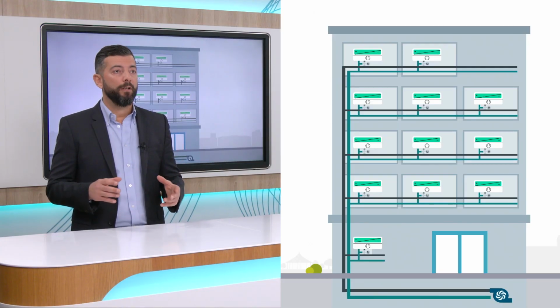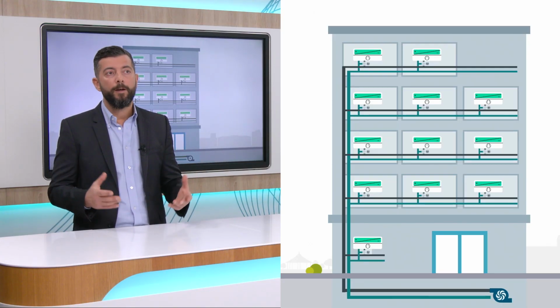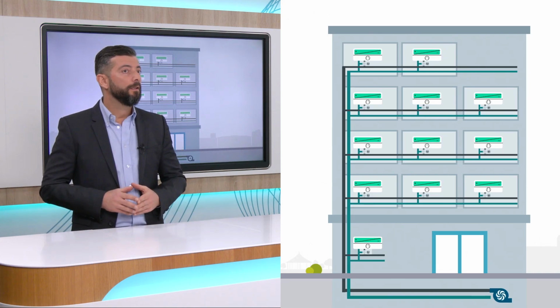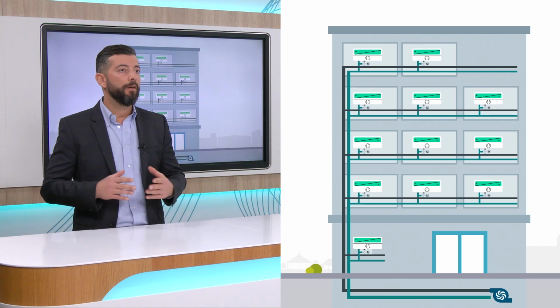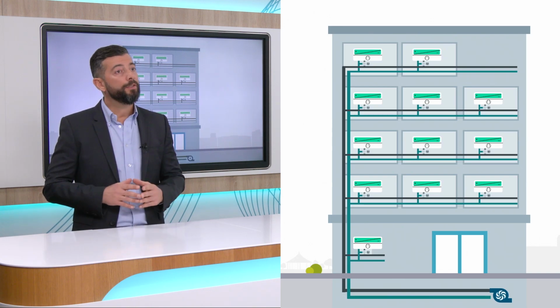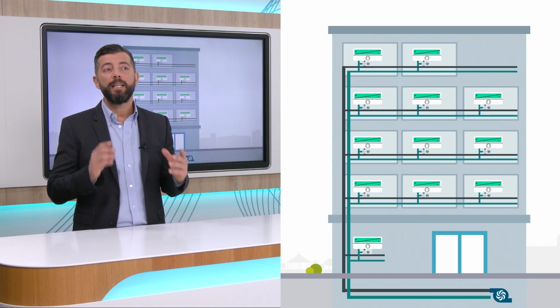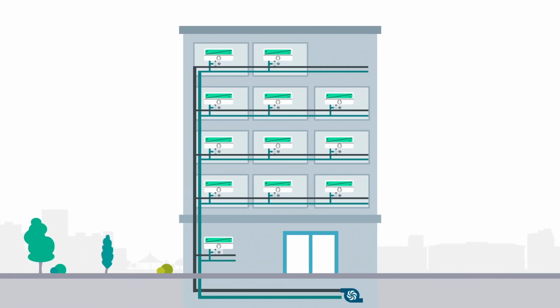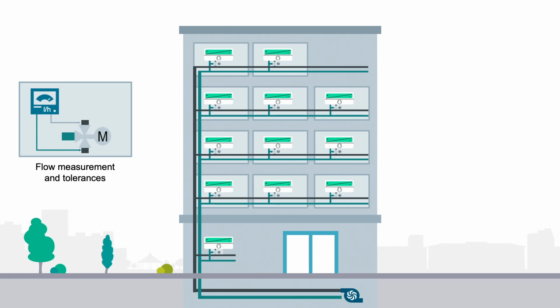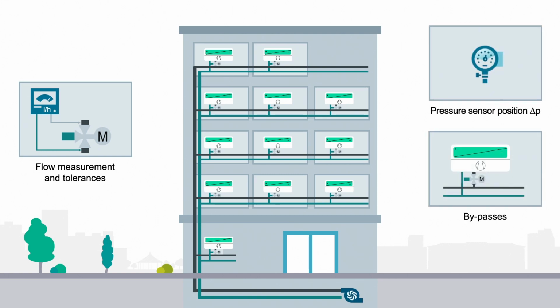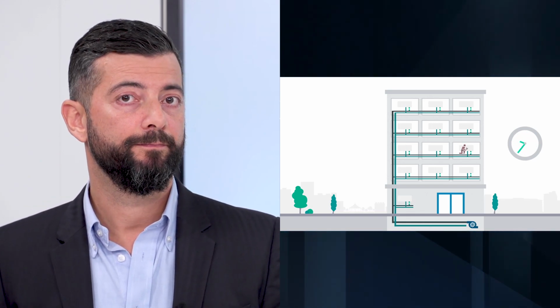The specific commissioning methodology and operational procedure depends on the local standards and relevant statutory and legal requirements. But there are certain considerations which are always valid simply based on physics: flow measurement and tolerances, pressure sensor position, and bypasses. Measuring the flow is probably one of the hardest challenges during commissioning and could lead to a lot of time-consuming work, disputes, or even legal actions between the different parties involved.